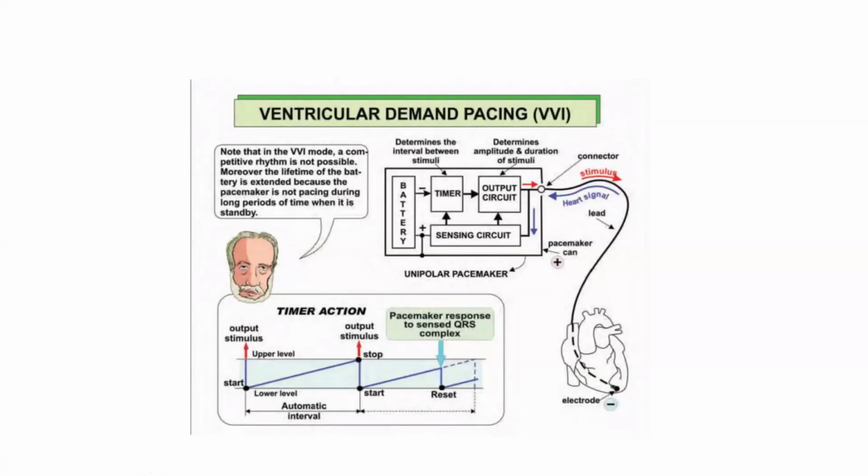It's like a man is sitting inside the pacemaker. This man was just counting and firing every fixed interval. Now this man can see. And if he sees the electrical activity or the QRS complex occurring inside the heart, he will stop counting, will reset and start counting again and will not fire for these beats.